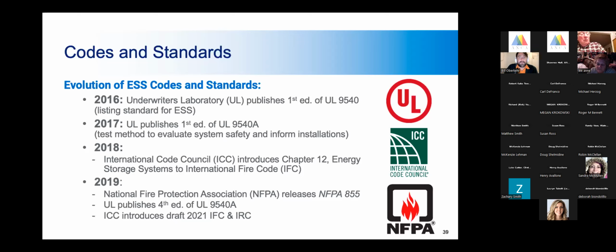What UL 9540 means is that every component of the system has been tested with each other. So the cell, the inverter, the fire suppression equipment, and the cabinet have all been tested together as one unified system, even though they're different components with their own UL listings. UL 9540 says that all of those components work together.